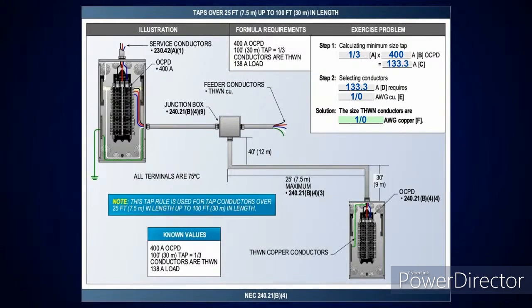And this one here, this is a 100-foot tap. And you'll notice we also put some rules in there for how that would be installed: 30 foot up above the panel board and all this other stuff, and then 25 foot back and 40. So we put all that stuff there if you want to reference. But in this case, we got a 400 amp upstream. Take it at a third. Everything that's left at a third.